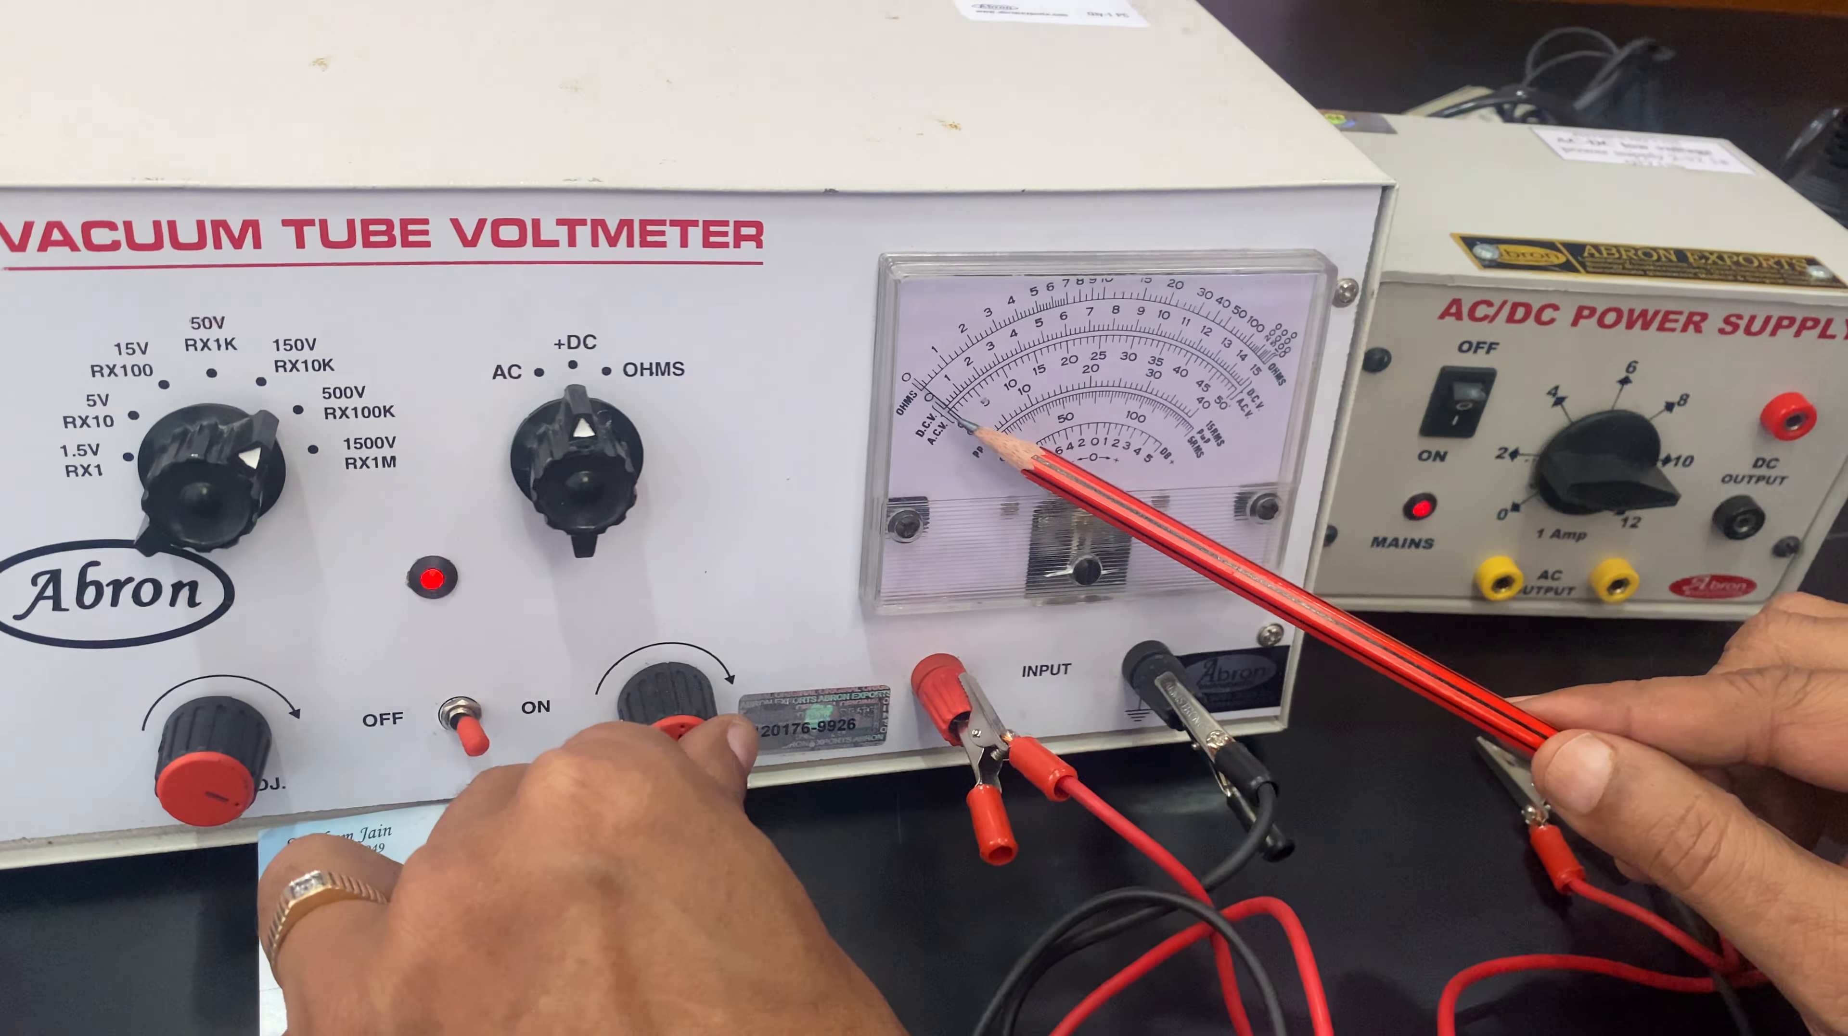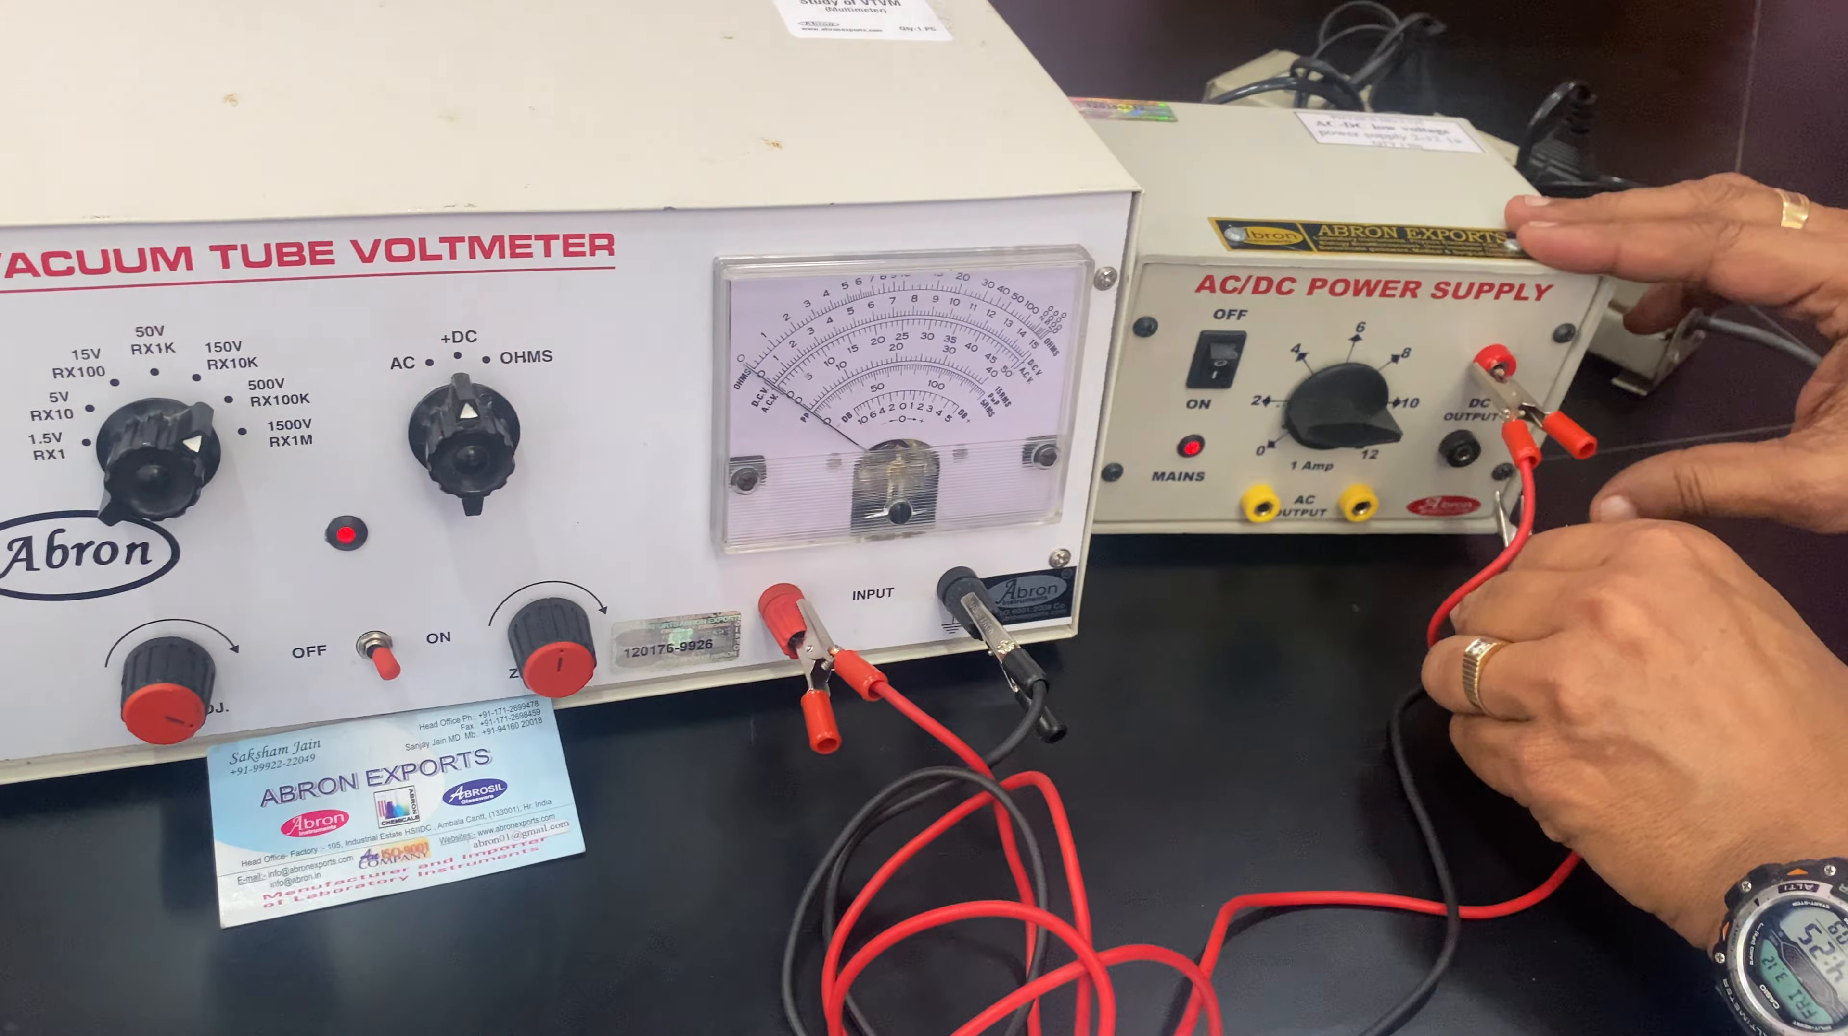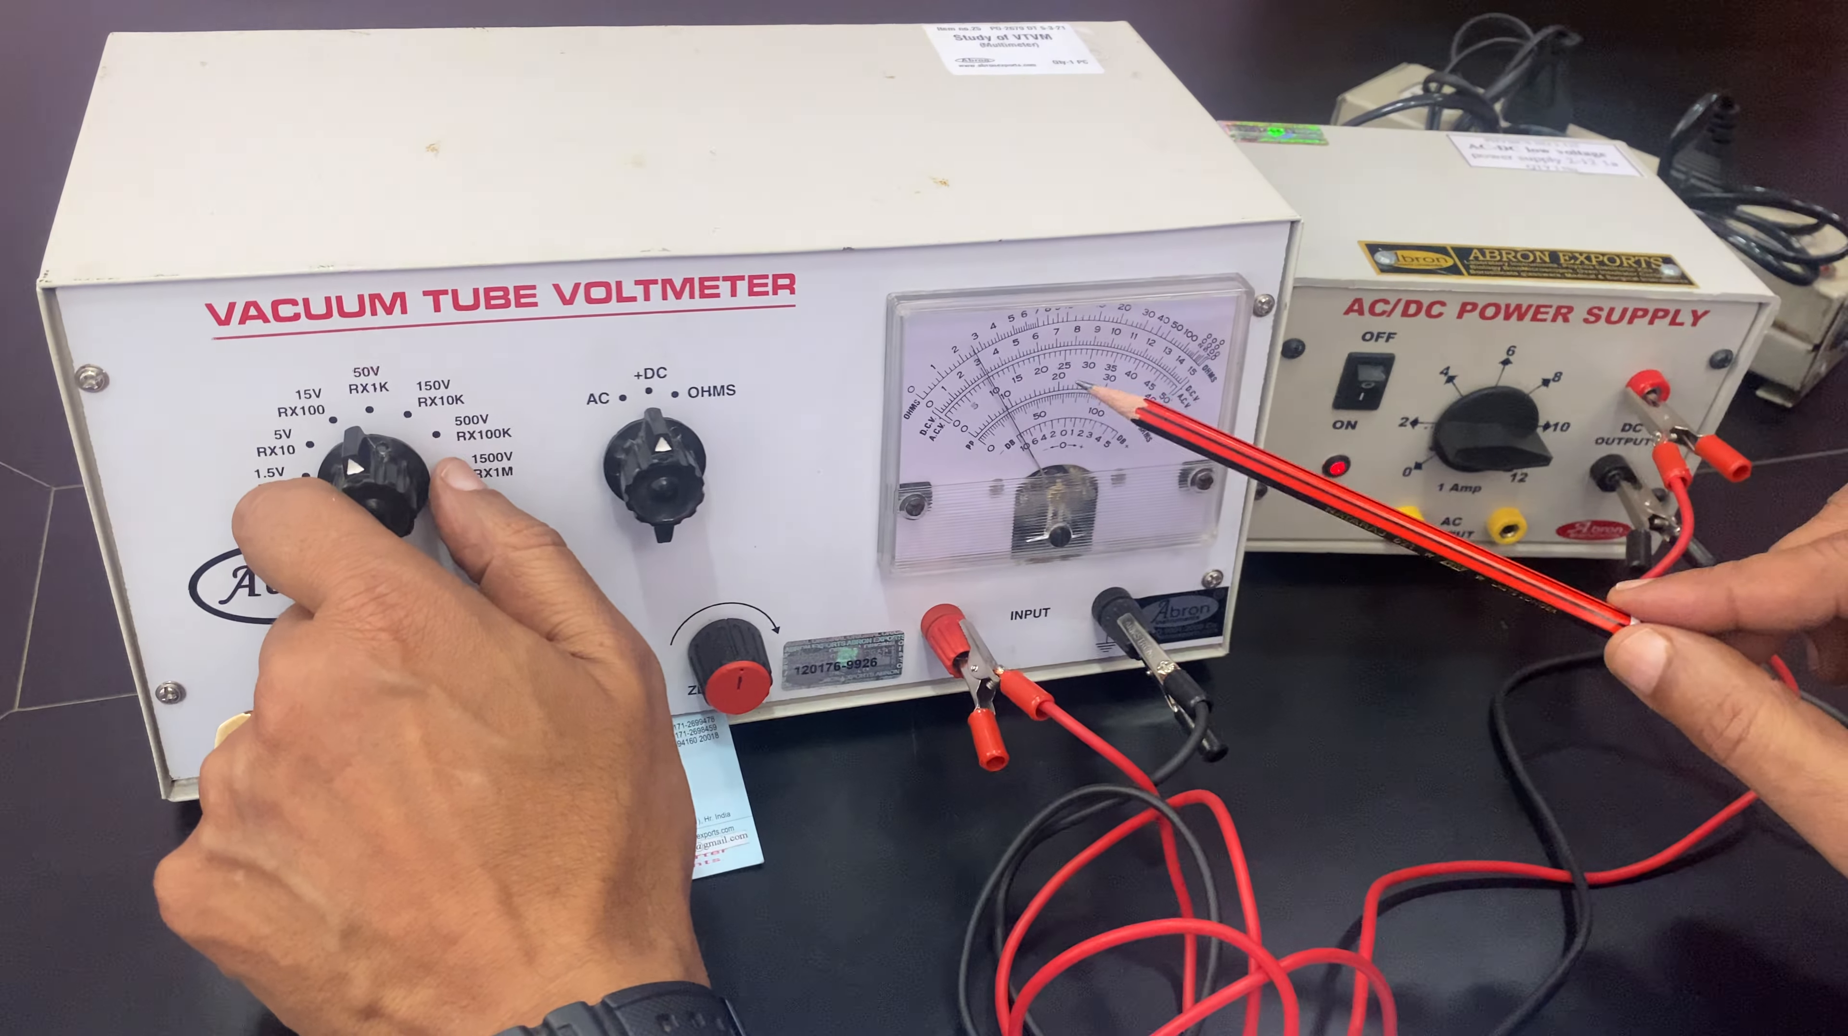First, adjust the voltage to zero. I have another power supply with me. I'm connecting this to the DC power supply. When I connect it, I use the DC setting and start with the highest voltage for unknown voltage. Now it's coming in range.